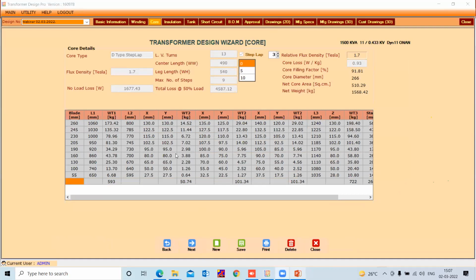Let's click on the next. So based on the winding information and the stack calculation and what kind of core type we have selected on the basic information page, this core card is generated automatically. Here you will get the information about core type, LV turns, center length, leg length, maximum number of steps, total losses at 50% load, then the relative flux density, then core loss, core filling factor, core diameter, net core length, area, and net weight of the core.